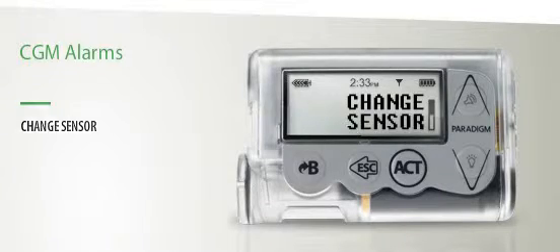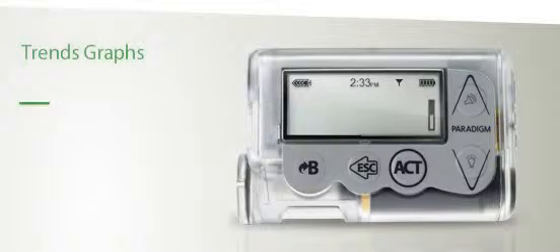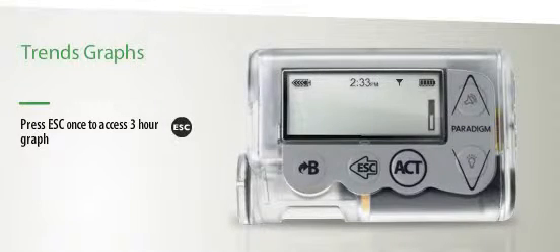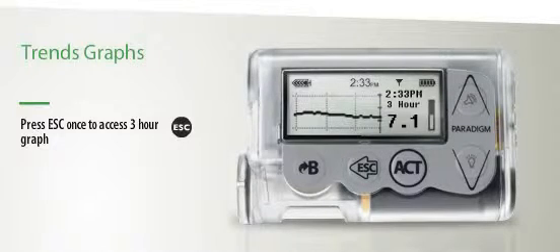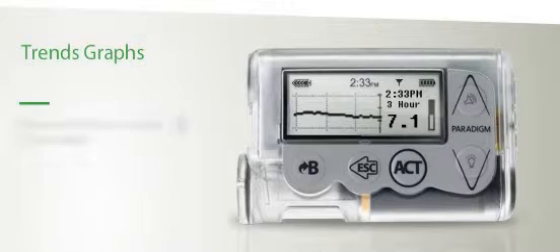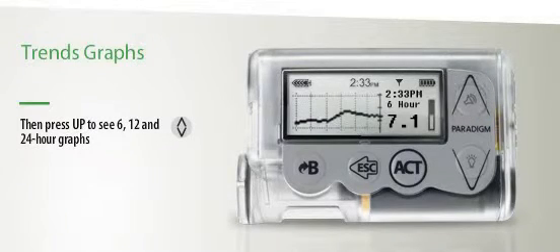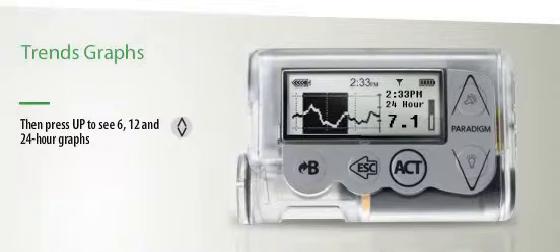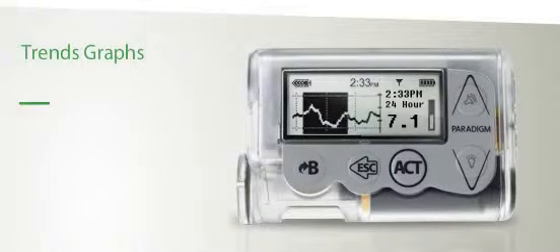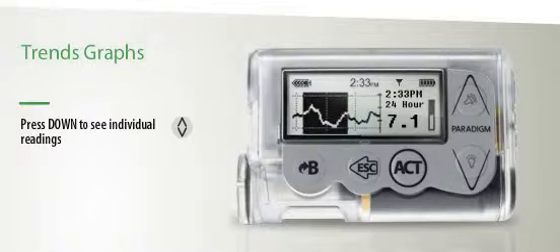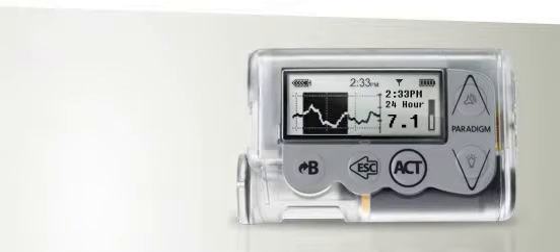Check the transmitter to make sure it's charged. To access your trend graphs, press the Escape button once. This will bring you to the 3-hour trend graph. To access the 6, 12, and 24-hour trend graphs, press the up arrow. If you would like to see individual sensor glucose readings while viewing a specific trend graph, press the down arrow.